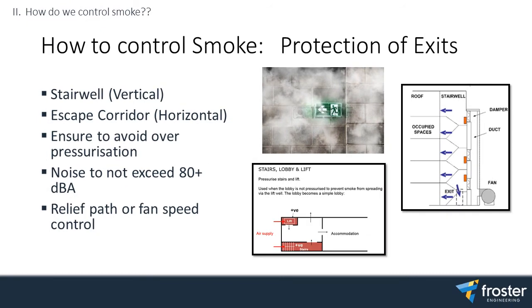Protection of exit, so a stair, escape stair, either vertical or horizontal. Again, know the building well. You're working with the architect. You have to identify, this actually comes from you. If you have an escape path, like I think the rule 60 meters, greater than 60 meters, then we have to pressurize that escape path. So again, we're working together on that solution. If you're planning it from the beginning with the architect, you might be able to get rid of that option.